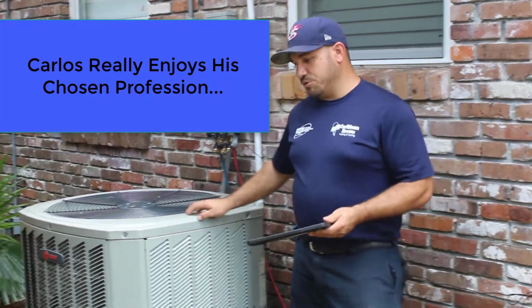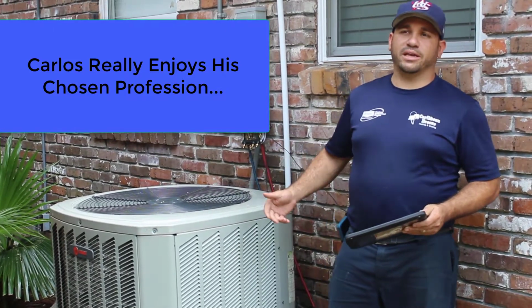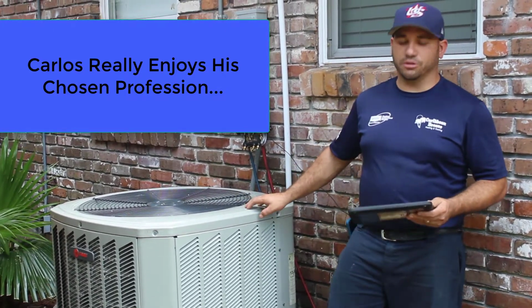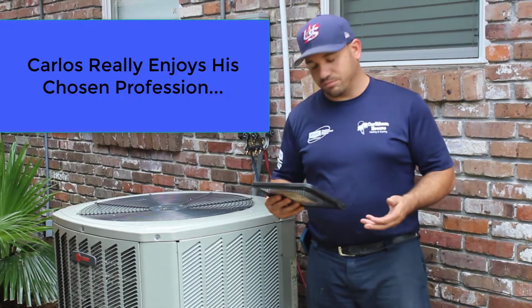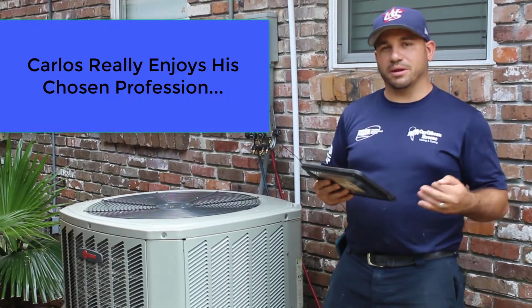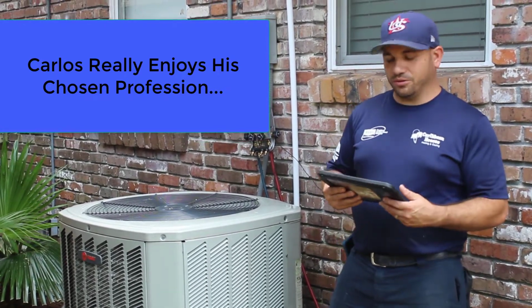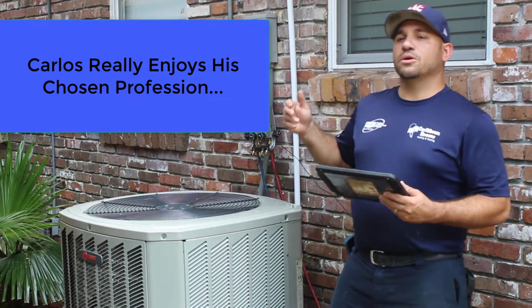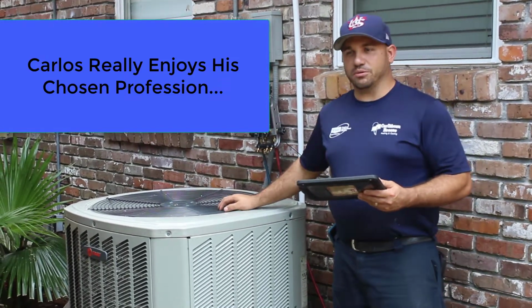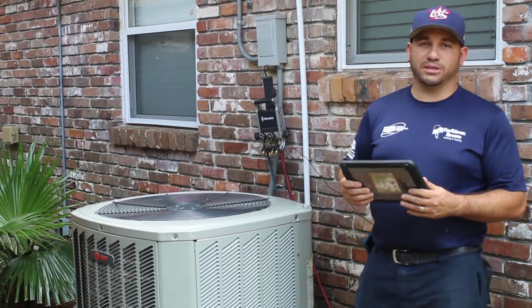Because as you can see, this unit right here is a Trane, it's matching equipment, and according to the manufacturer's specification, the required subcool on this unit is 10 degrees. And right now we're only getting 2.7 to 3 degrees subcool. So it just shows it may be a little bit undercharged. So we might have to add probably an ounce or two to the system to get it to the proper charge as the manufacturer requires, and that way the unit can work properly and to its maximum efficiency and BTU rating.